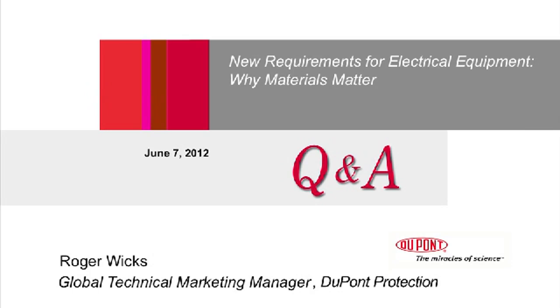In terms of high temperature, as I mentioned earlier, it's a time-temperature relationship. We age Nomex paper in temperatures from 260 to 320 C to enable us to get our rating of 220 C, which is good for 100,000 hours life. In terms of humidity, we do a lot of evaluation of Nomex under humid conditions, and typically our materials are very good in terms of their characteristics, even under high humidity conditions. That information is available in our technical data sheet, for example, our Type 410 papers.